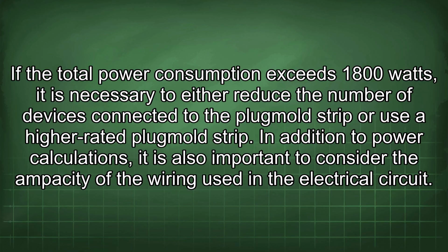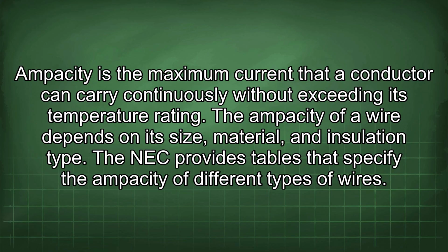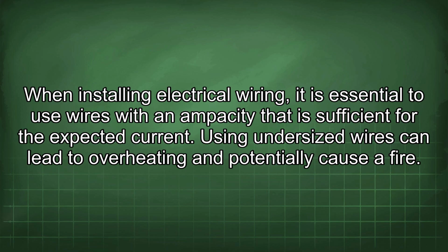In addition to power calculations, it is also important to consider the ampacity of the wiring used in the electrical circuit. Ampacity is the maximum current that a conductor can carry continuously without exceeding its temperature rating. The ampacity of a wire depends on its size, material, and insulation type. The NEC provides tables that specify the ampacity of different types of wires. When installing electrical wiring, it is essential to use wires with an ampacity that is sufficient for the expected current. Using undersized wires can lead to overheating and potentially cause a fire.